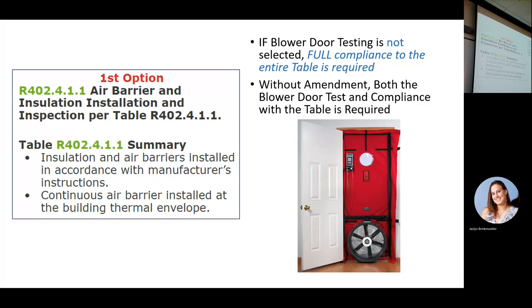And it's kind of slick because most of the time they do negative pressure. So they suck the house down 50 pascals, so it's 50 pascals lower than outside. And so we get the leakage in. And you can take little smoke things or theatrical fog machines, or you can take a thermal camera and you can detect where we have the cold or hot air coming through the wall, around the windows, through the plugs, coming down from above. And so you can measure how much leakage you have, and it helps you find out where you need to fix it.